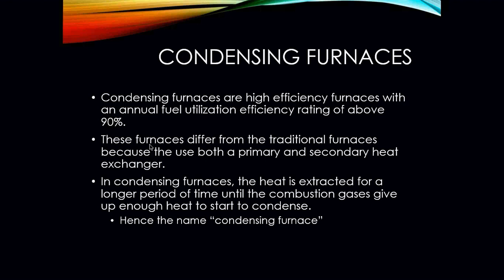Condensing furnaces have a fuel utilization efficiency above 90%. These furnaces differ from traditional furnaces simply because they have both a primary and secondary heat exchanger. The heat is extracted for a longer period of time until the combustion gases give up enough heat to start to condense. On your condensing furnaces, flue gases are around 100 degrees — sometimes even 90 degrees. The reason we achieve that is through the secondary heat exchanger, where the air passes through that portion of the furnace longer, allowing us to pick up that additional heat and put it into the space.